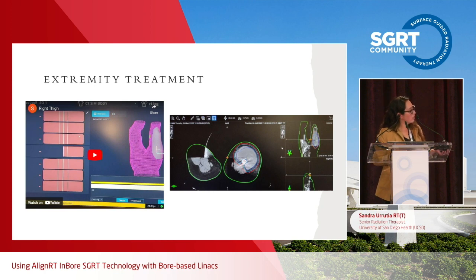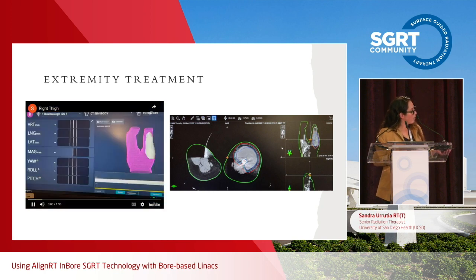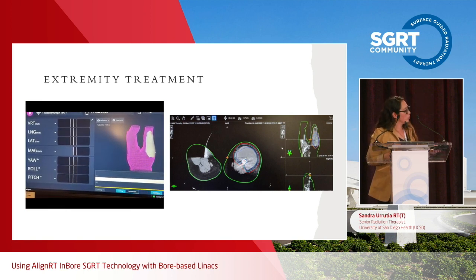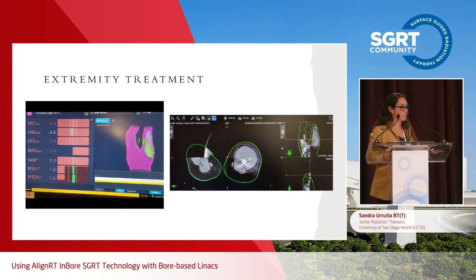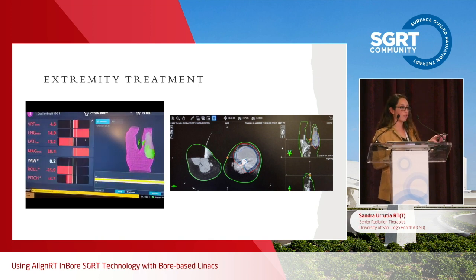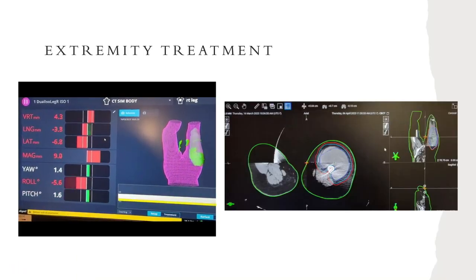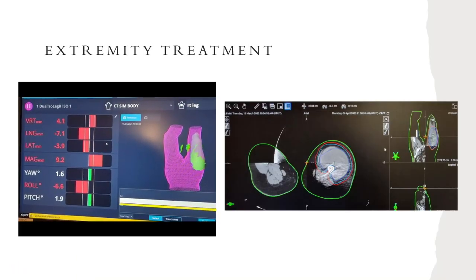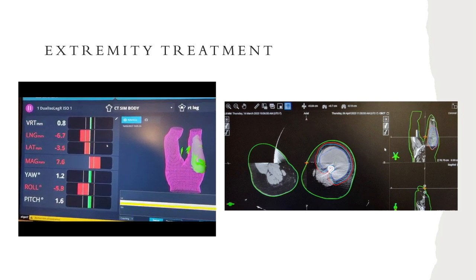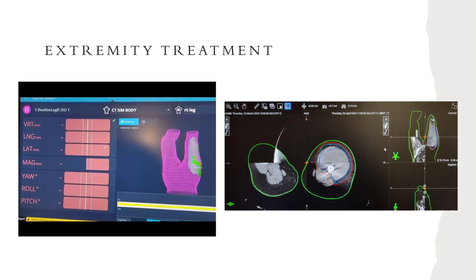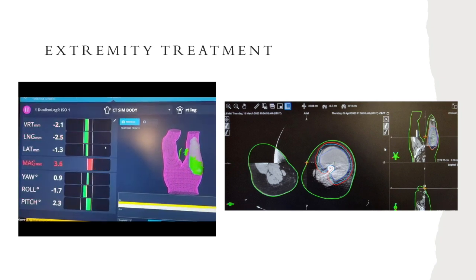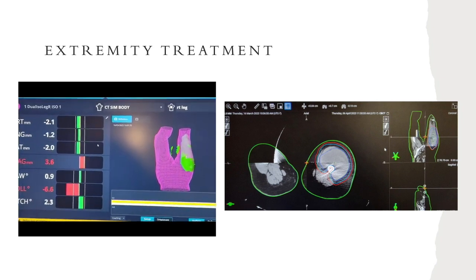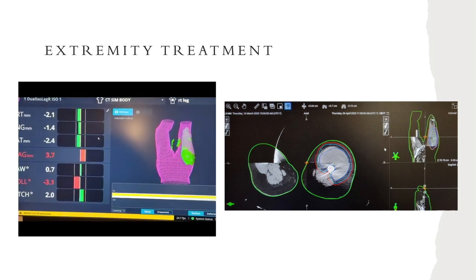And you'll see here in the video in a moment, it takes a little bit longer for the therapist to get the patient in position. And right now it's a little glitchy because we're so far from setup ISO. It's difficult for the cameras to read. But once we get a little bit closer, we can fine tune the patient's position, again using the vert, the long, and the lat, adjusting those by using the controls on the machine, and adjusting the yaw, the roll, and the pitch by manually moving the patient's leg.